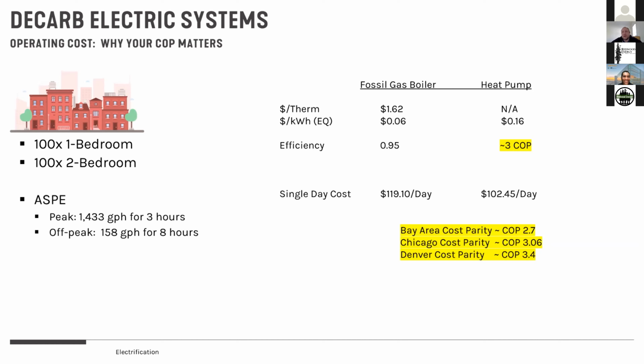So here, if I was just running a quick calc on what's it going to cost my client to make hot water for this project, 200 unit apartment, it's about $100, $120 a day if they're using fossil gas. If I have a COP of 3, annually averaged out on a heat pump, I can reduce the operating cost of the system. It's when I promise a COP of 3 and deliver a COP of 2 during the winter that cost parity drops off quite a bit. And it becomes far more apparent when we move outside of California's utility cost regime. So in the Bay Area, looking at PG&E rates for this size project, if I can hit a COP of 2.7, I'm on cost parity with a fossil boiler. So I can win the day if I design a system that can readily achieve a 2.7 or better.